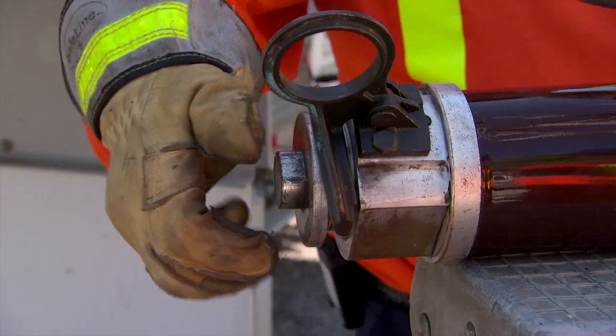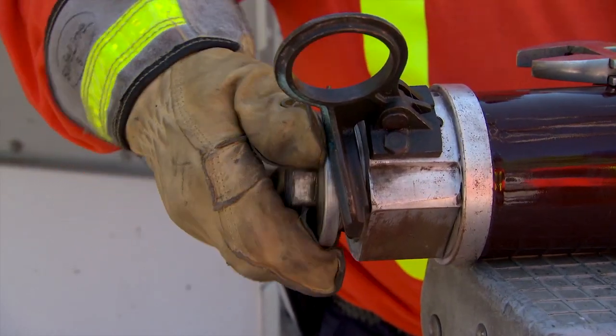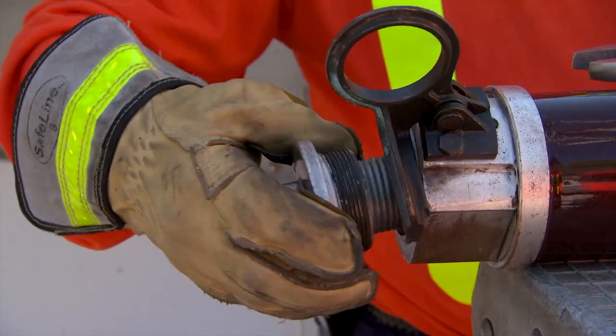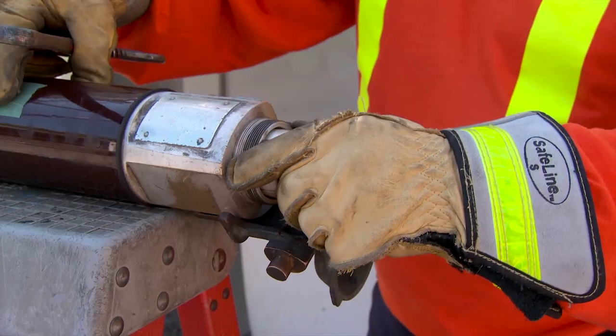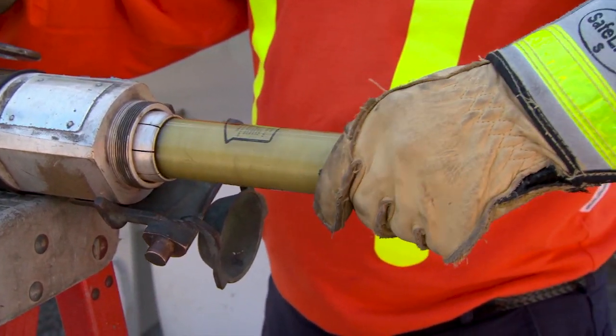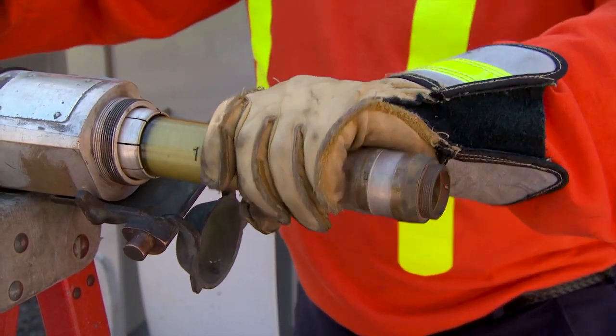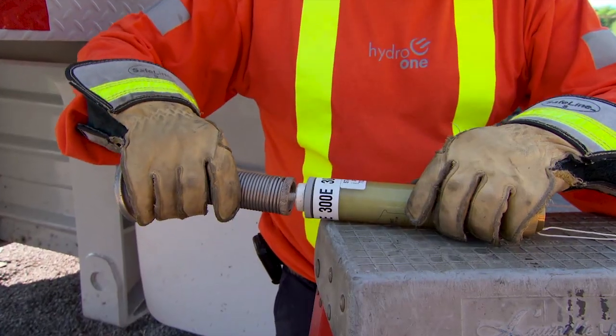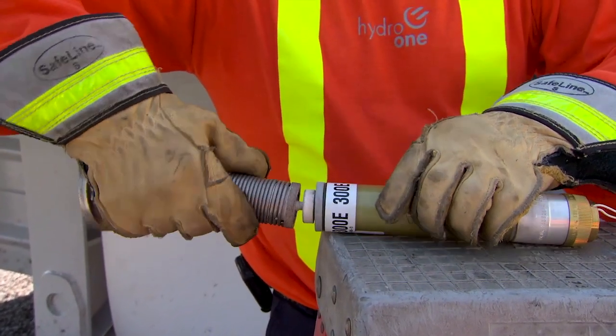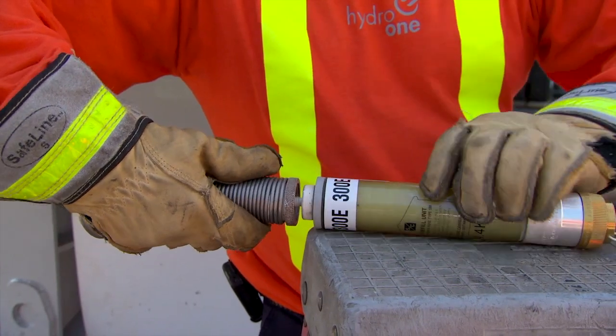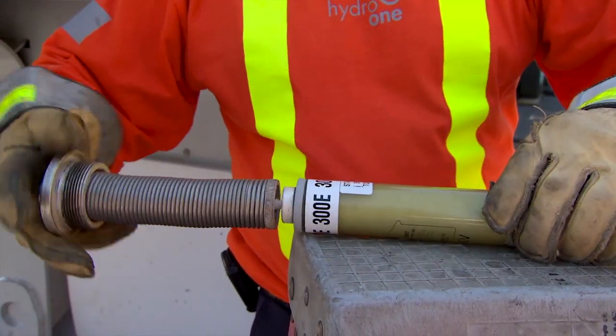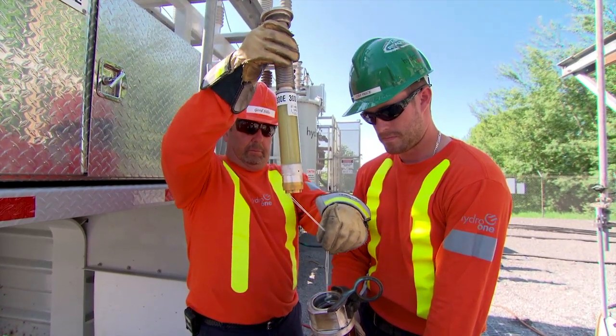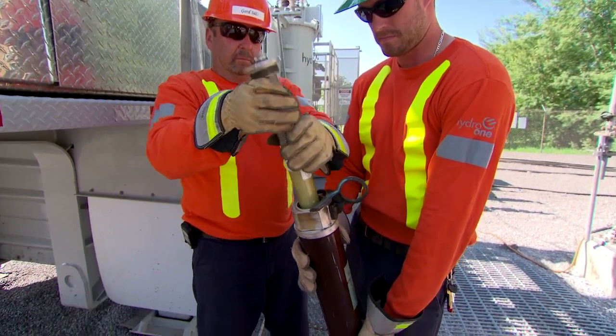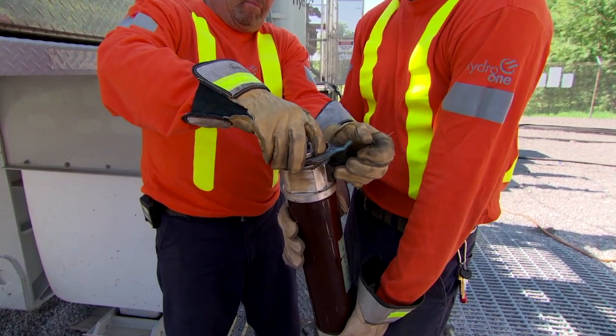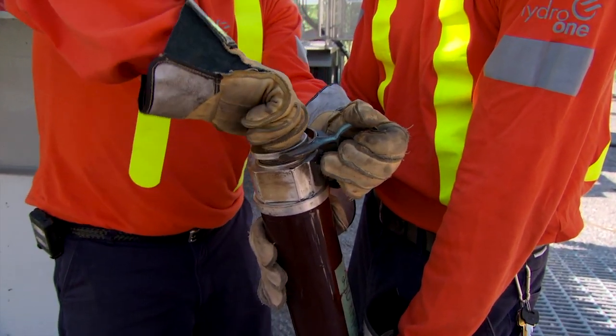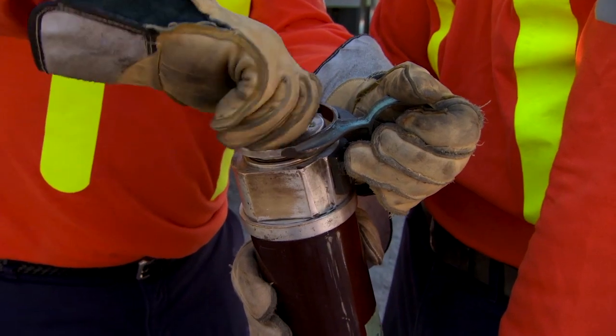Using basic hand tools, disassemble the fuse holder and remove the existing fuse element. Thread the newly selected fuse element onto the spring mechanism and tighten by hand. Holding the fuse barrel vertically, insert the fuse element and spring mechanism into the fuse holder, making sure that the string exits the other end. Thread the fuse spring combination into the fuse barrel and tighten.